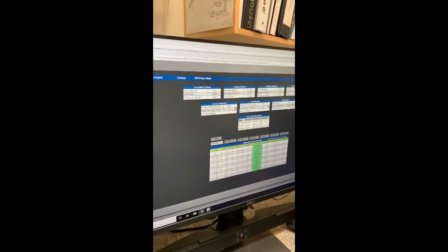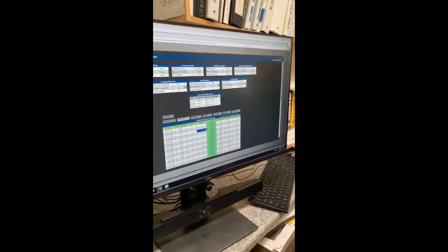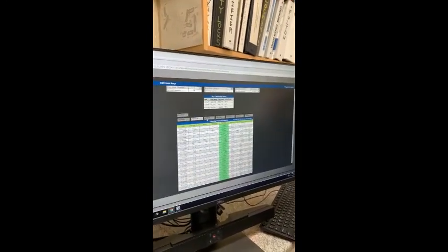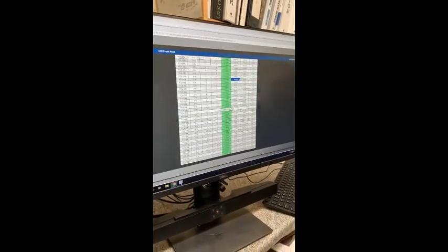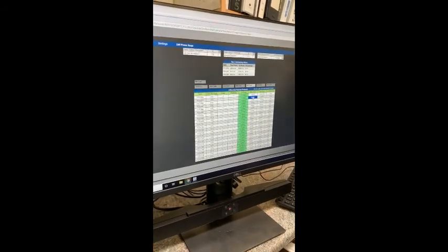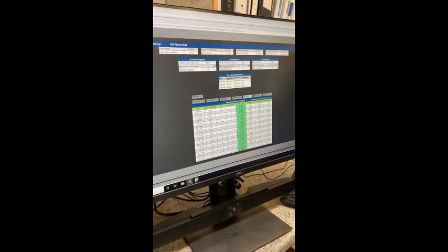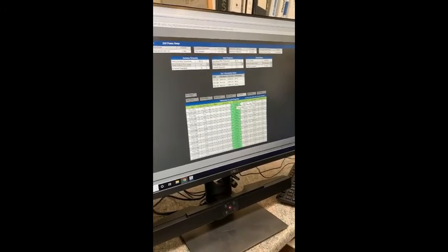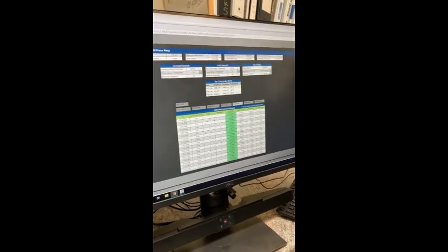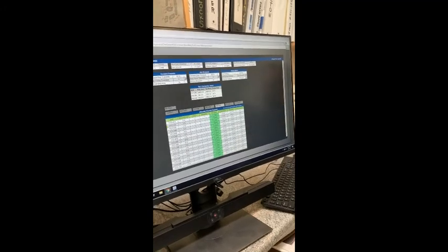In the chilled water and hot water systems, you can see who's requesting, and you can search through floors. Right now no one is requesting an increase. Everyone's saying, hey, you can decrease as far as I'm concerned. This is what they call a negative request. It's basically saying I don't need more, I'm good. I'd be fine right now.